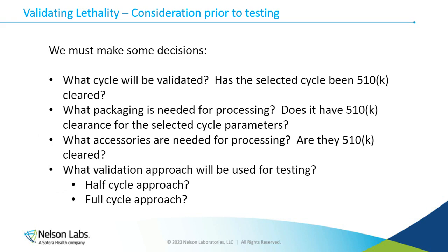When validating lethality, we need to make some key decisions before we start testing. We need to decide what cycle will be validated. Has the selected cycle been 510(k) cleared — is it part of a machine that has been 510(k) cleared? What packaging do we need, and does that packaging have 510(k) clearance for the selected cycle parameters? What accessories are needed, and are they 510(k) cleared? And what validation approach will we use? The half-cycle approach is very commonly used for these device types, while the full cycle approach is used less commonly and tends to be better applied in industrial validations.